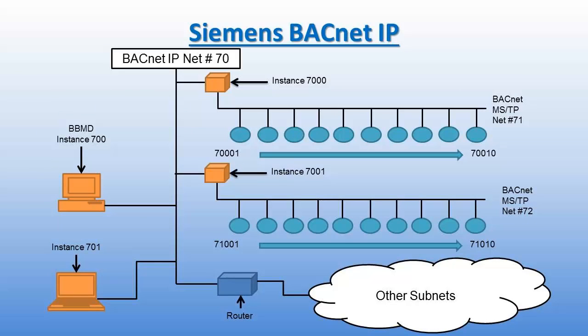This is the Siemens BACnet IP diagram, drawn up by a Siemens employee that maintains networks for HVAC. As you can see, there are many different instance numbers on a network — some for a router, some for a switch, and some for small controllers. The computer on the left-hand side, which has the instance number of 700, is configured to be a BBMD, which will be discussed in the next slide. As shown, there is both BACnet MSTP and BACnet IP present — BACnet IP is a subnet, and BACnet MSTP is a subnet of a subnet.